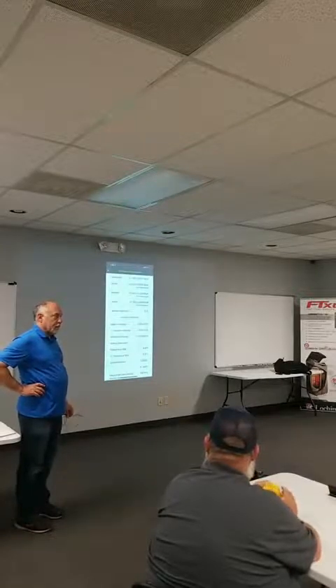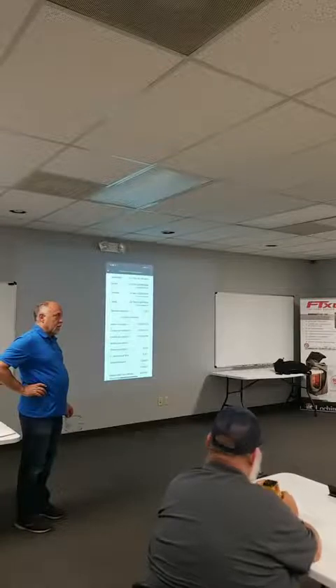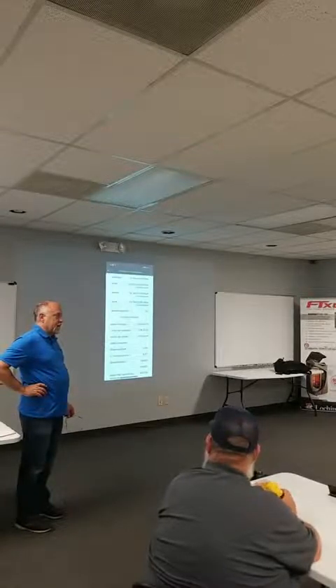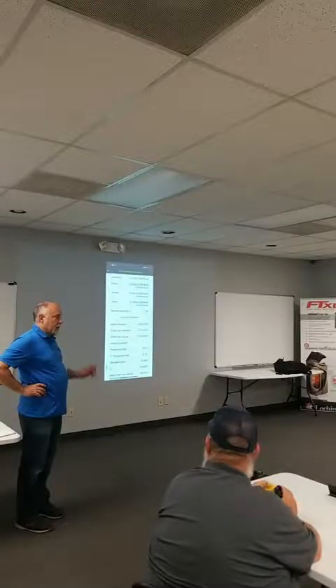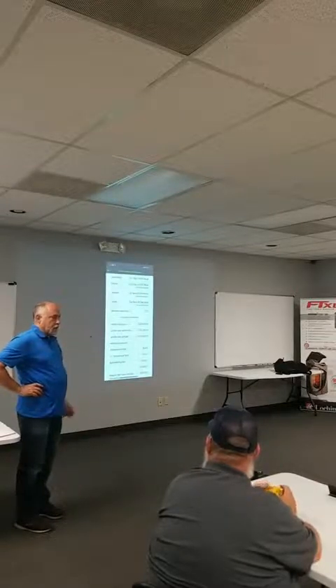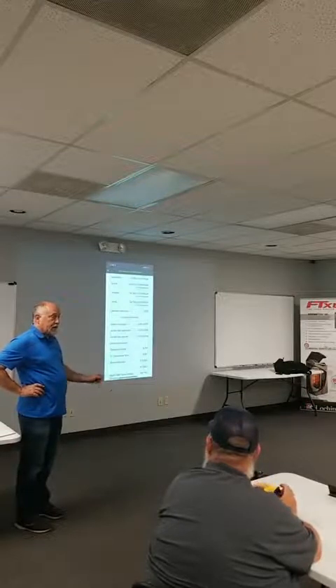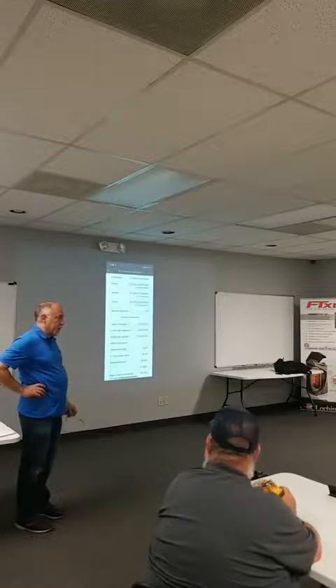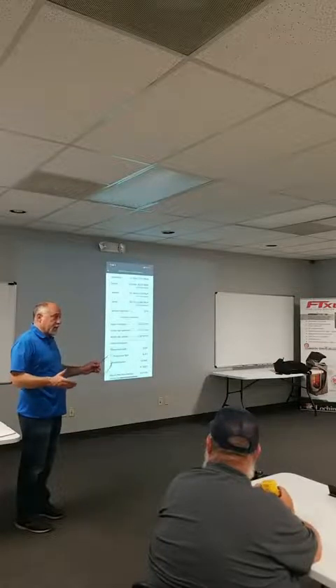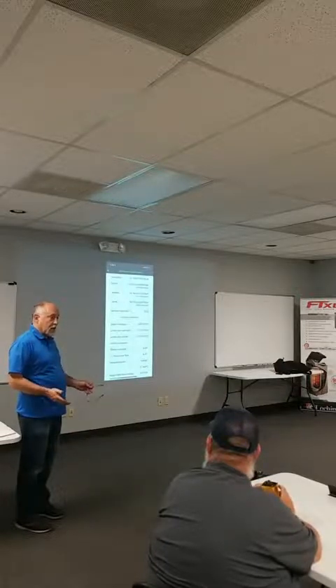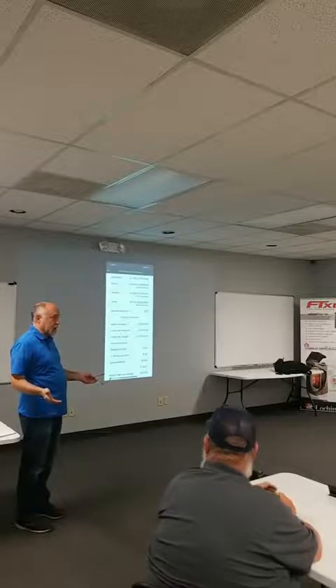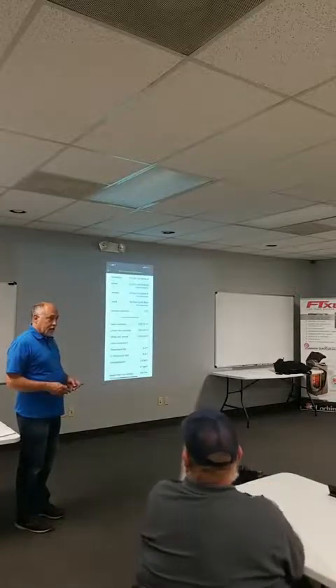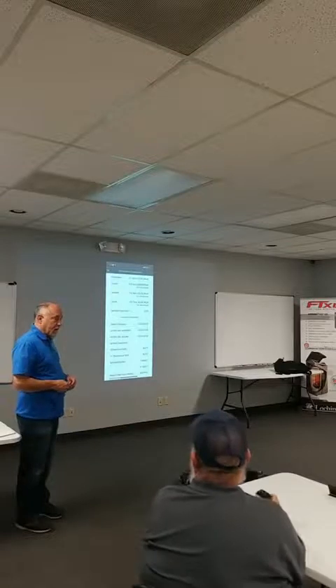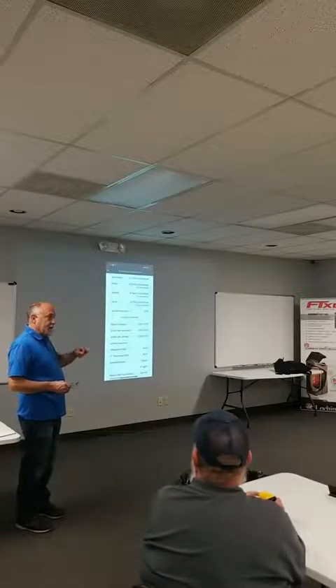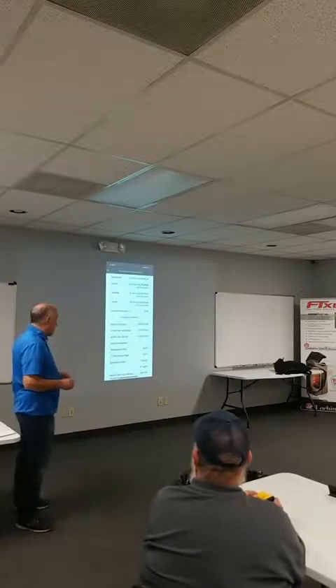68 degrees, 50% humidity. A standard CFM has a mass of 0.075 pounds per cubic foot. We're not cooling CFM of air, we're cooling pounds of air. 0.075 times 400 is 30 pounds per minute per ton. So you're actually cooling 30 pounds of air per minute going across the coil, or if it's a 5-ton system, 150 pounds of air per minute going across the coil. That's where the location, altitude data and all that come in. That's mass flow, right? So if you took 0.075 times 2,000, it's 150 pounds of air.